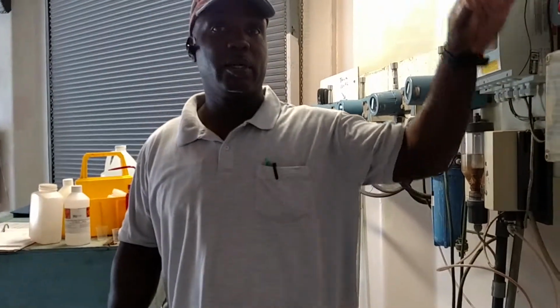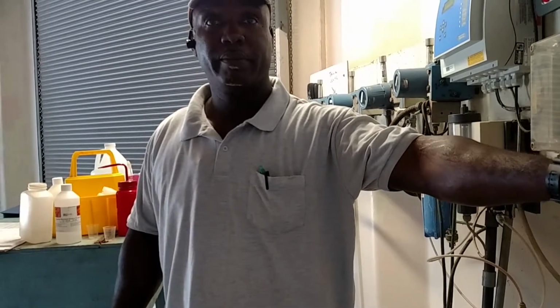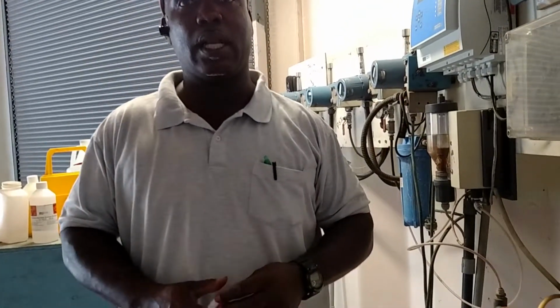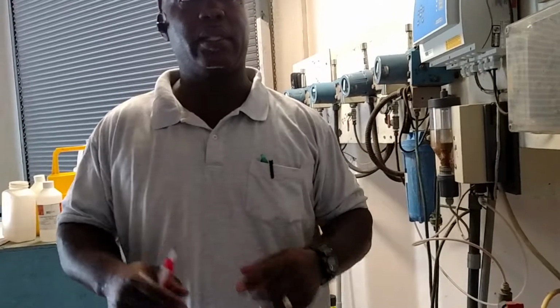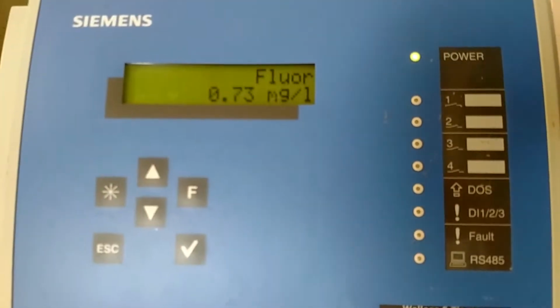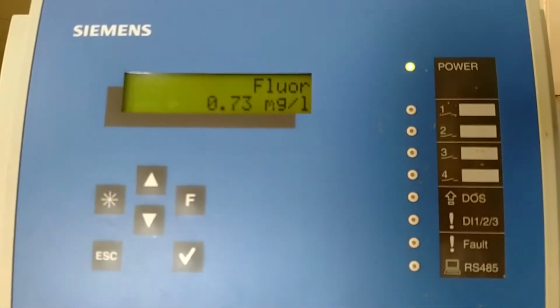Okay. But I found out that sometimes I've had it in span, I had it while I was calibrating it, and then it timed out. It was reading something different on the sample, but it was reading it different for the standard. But when I put it back in span, calibration mode, it was reading a lot higher. Oh. So it wasn't actually reading the same thing. Okay. This is a good number. 0.7 is the target. Yes.